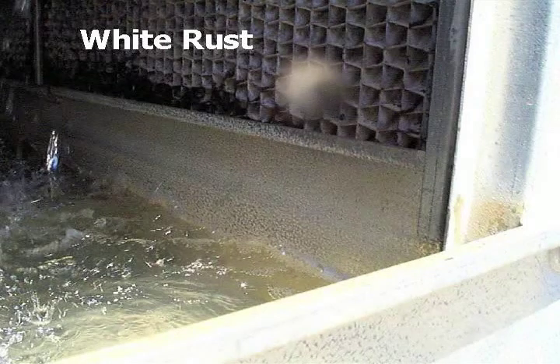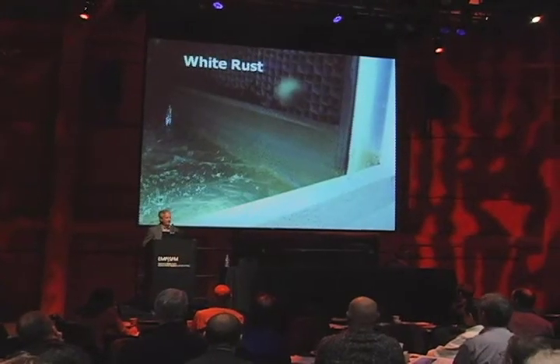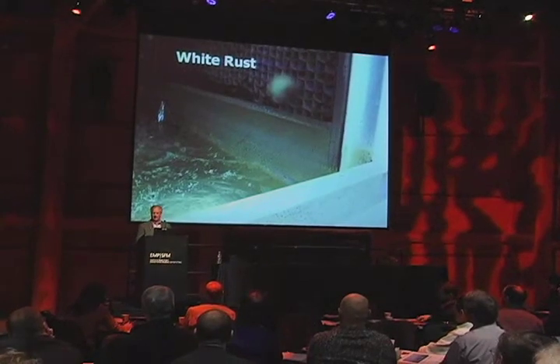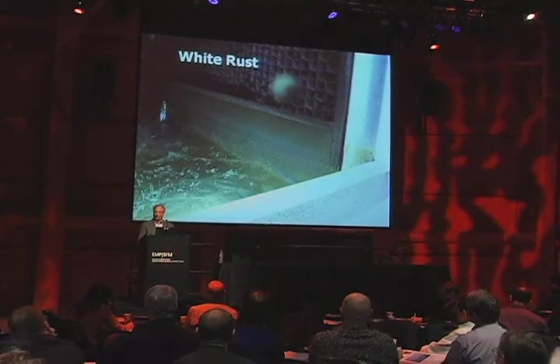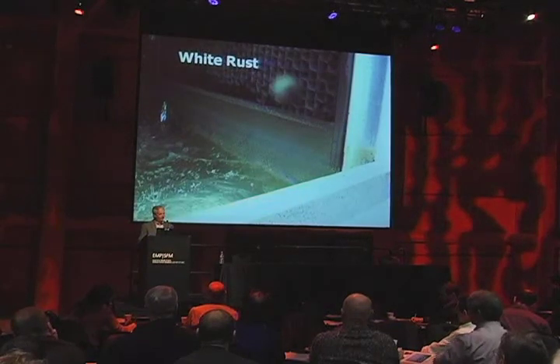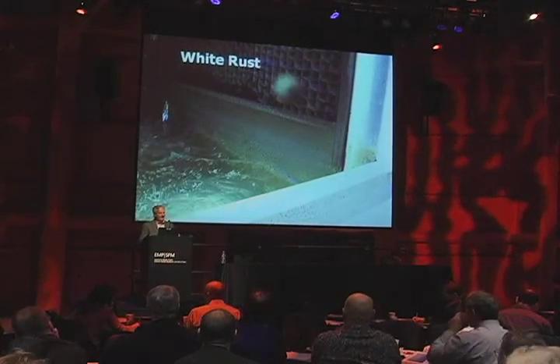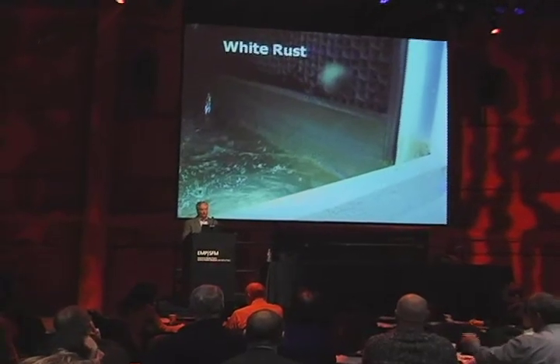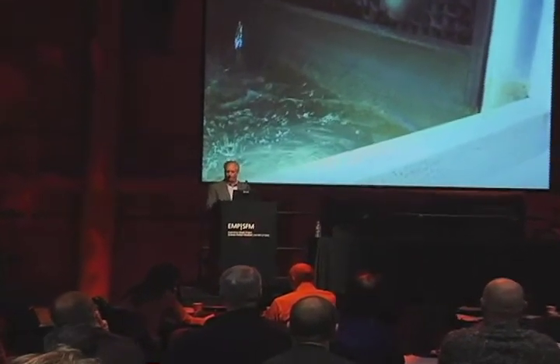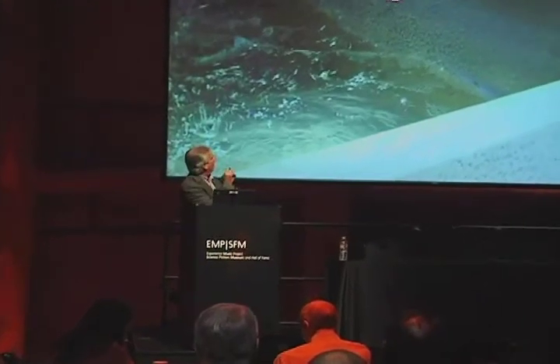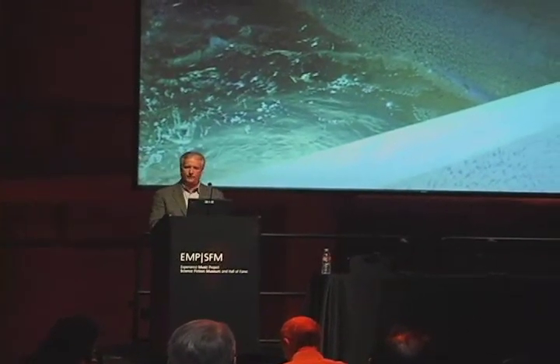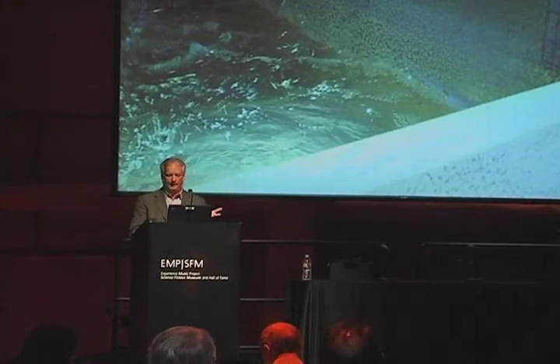How many people have galvanized towers here? How many people see white rust here? Okay. Basically, white rust is zinc carbonate, okay? These towers are coated with galvanized, and the galvanized is basically a sacrificial metal. That's its design. Its design is to protect the under metal surfaces of the cooling towers, so they coat it with zinc. Well, zinc does not like high alkaline water, okay? And so it forms zinc carbonate, which are white bubbles, rust pockets, basically on the surface. So you're basically leaching out zinc and forming zinc carbonate.